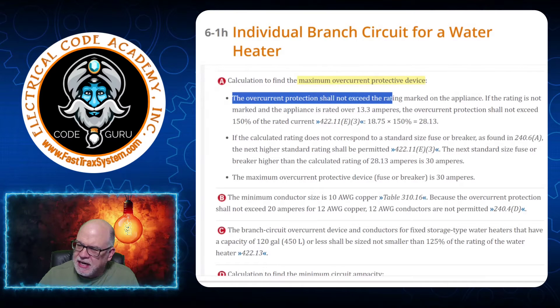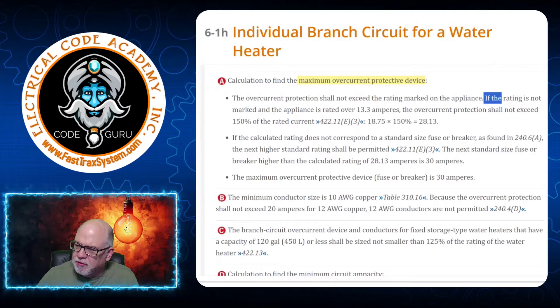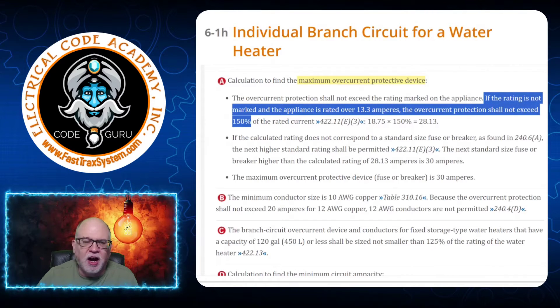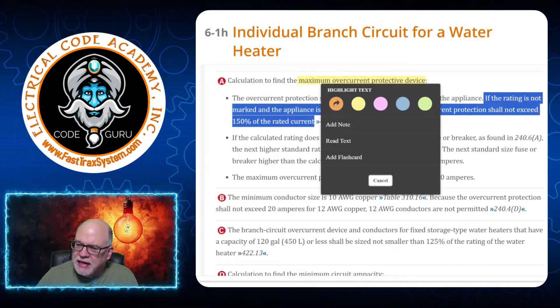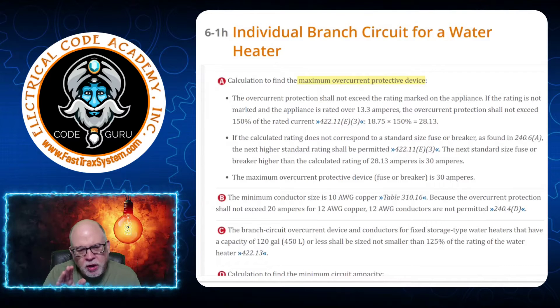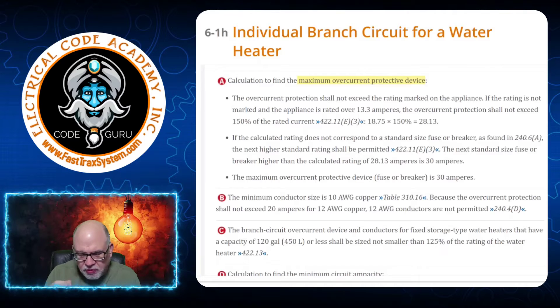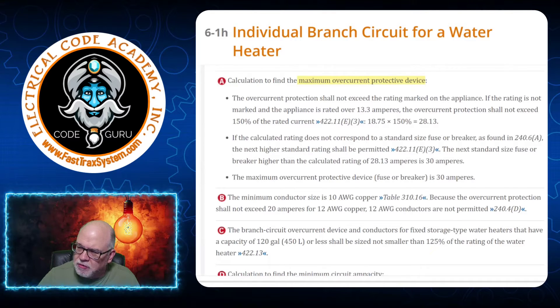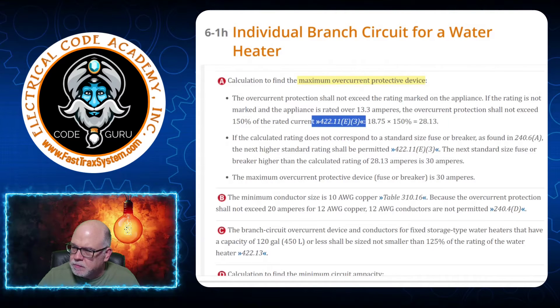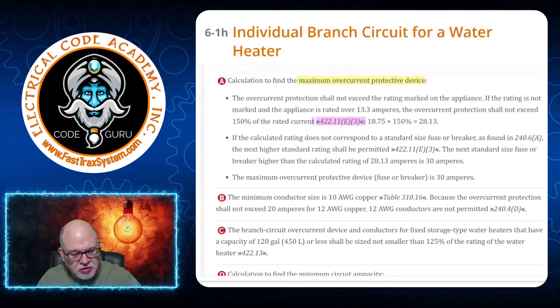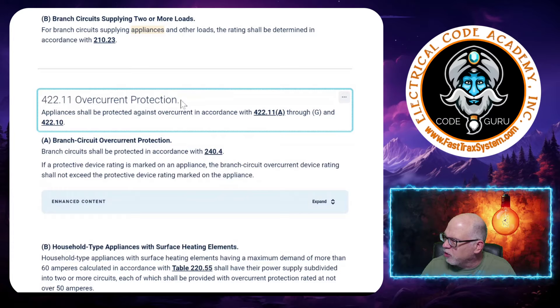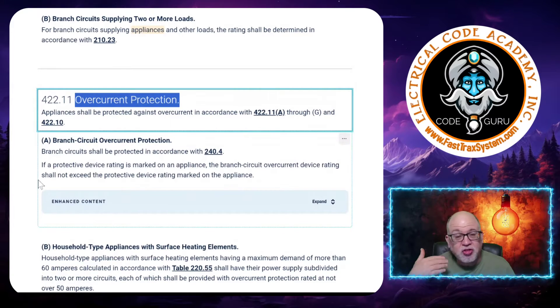The overcurrent protection shall not exceed the rating marked on the appliance. If the rating is not marked and the appliance is rated over 13.3 amperes, the overcurrent protection shall not exceed 150% of the rated current. A water heater is an appliance, so it's covered under Article 422. Let's go to the NEC — here we're at 422.11, talking about overcurrent protection for this water heater and the circuit supplying it.